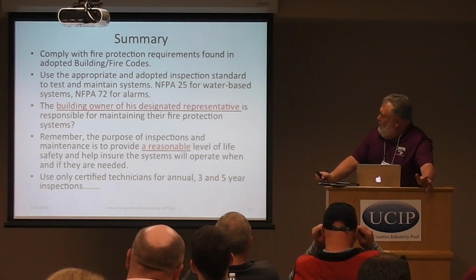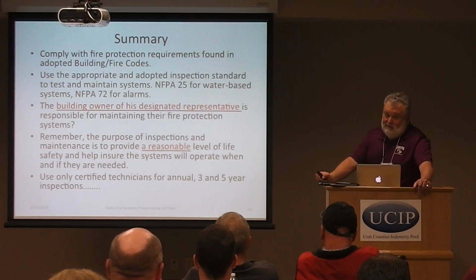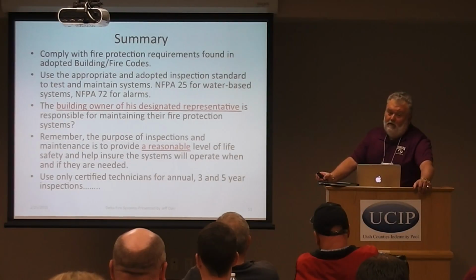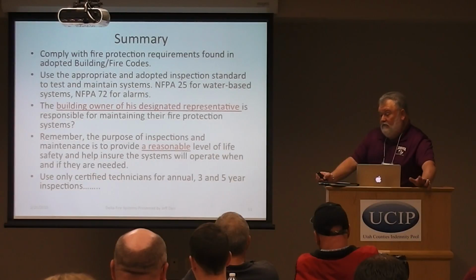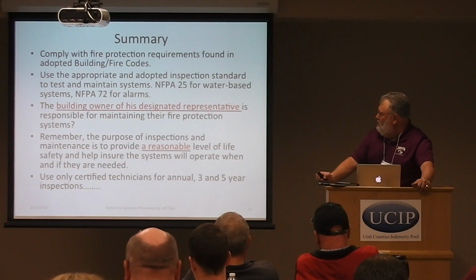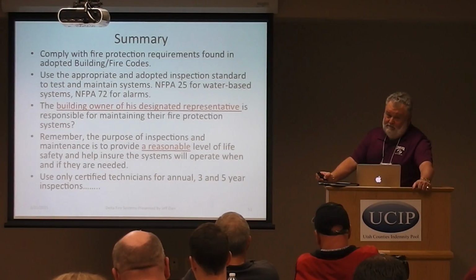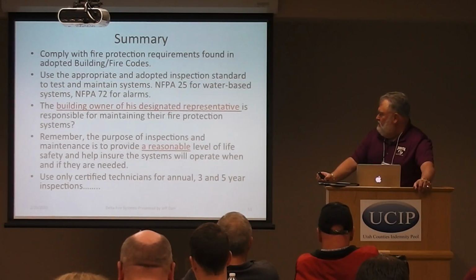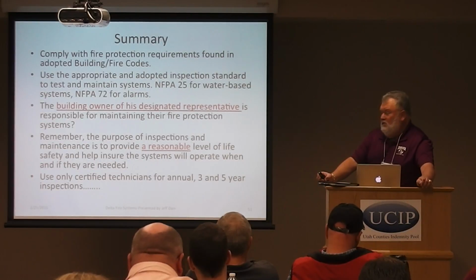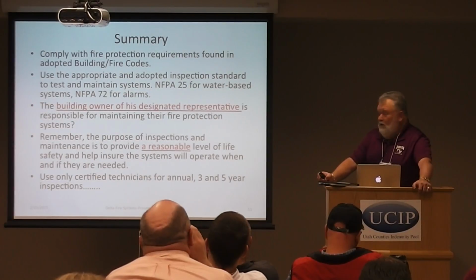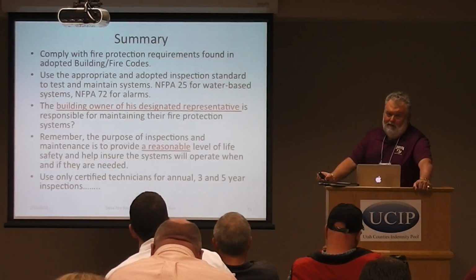And in summary here, I just wanted to stress a few things again. Sprinkler systems are installed because they're usually a code requirement. And once they're installed, we have to make sure that we use the appropriate and adopted inspection standards to test and maintain the systems. The building owner or his designated representative is responsible for maintaining their fire protection system. You can hire that to be done, you can have your own qualified people do it, but ultimately it's that owner that's responsible. And then we only have to do the inspection and maintenance as a reasonable level of life safety. We want to make sure that that system will operate if it's needed.